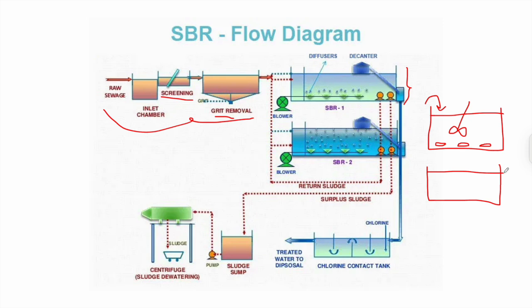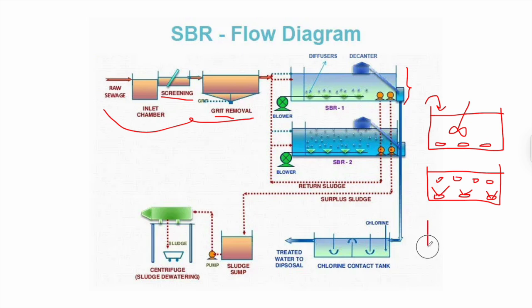The second stage is aeration. Using the same diffusers already in the tank, aeration begins, promoting the proliferation of beneficial bacteria. These bacteria form flocs within the wastewater. In stage three, aeration is stopped and the flocs are allowed to settle down by gravity.